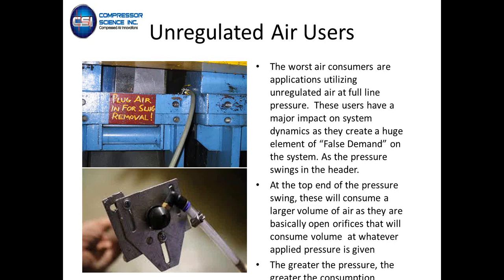So if you have a 1,000 CFM system at 100 psi, and you've got 10 users that are open orifices that are using compressed air at 100 psi in a 1/4 inch line, you're going to consume 80-90 CFM on those unregulated users. If you can regulate, even without getting into engineered nozzles, if you can regulate that application down, or those air guns or those air nozzles down to 50 psi, it would probably do just as good a job at 50 psi as it does at 100, but the impact on the system obviously is greatly diminished because everything's a function of applied pressure. So when we go in and we audit compressed air systems and we look at the pressure in the distribution system, we measure the flow.